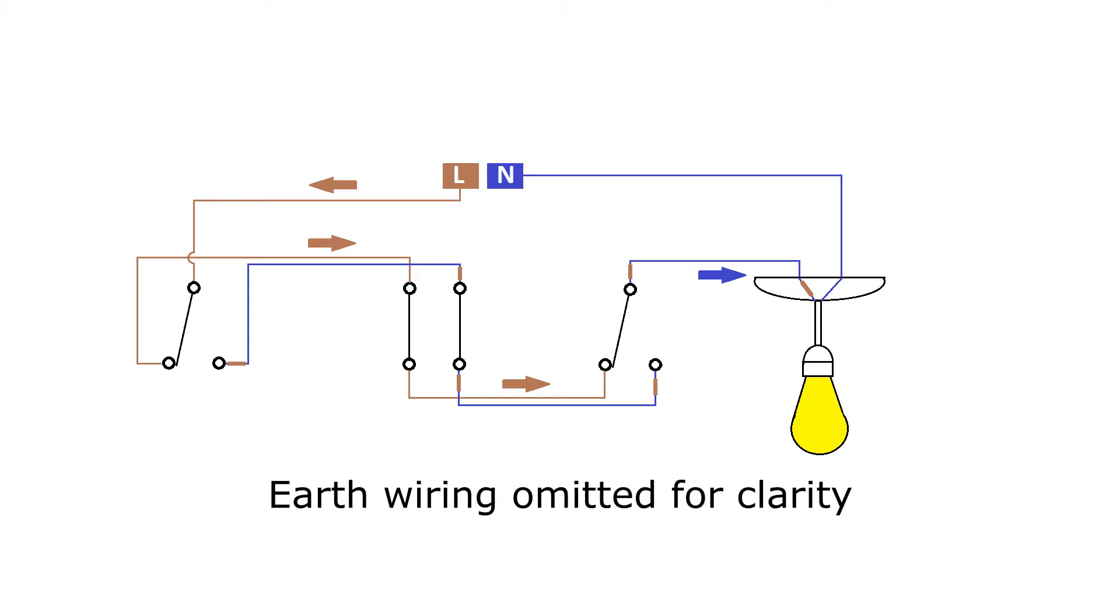Only the L1 and L2 terminals are passed from switch to switch. Once again, if more switches are required, that intermediate wiring is repeated as many times as is needed, with the two-way switches still at each end of the run.